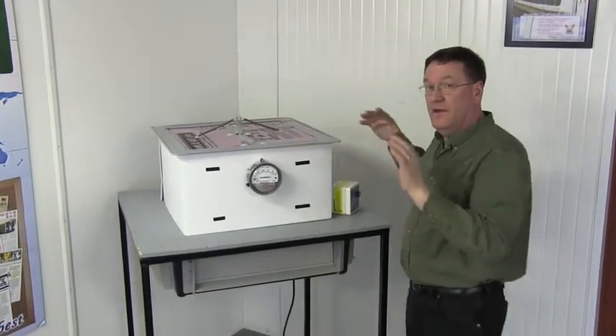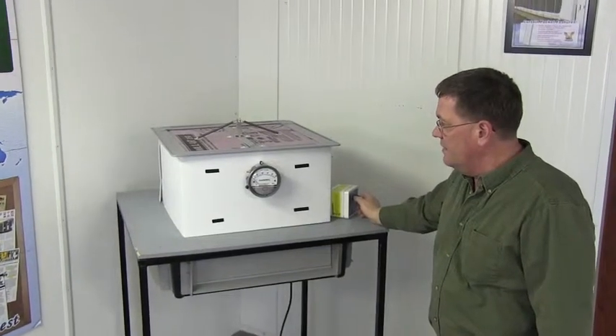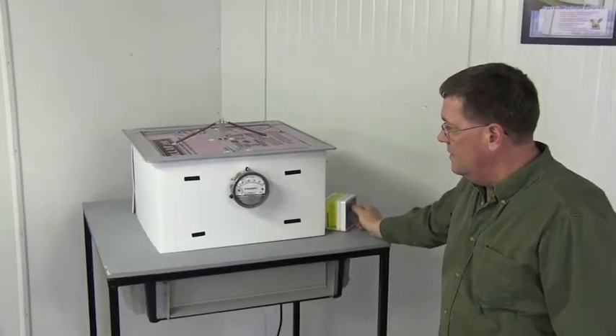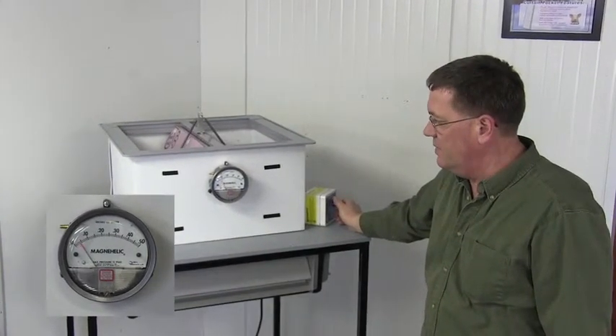You set this right on top of your attic sleeve that's already up in the attic. Once your fans kick on, it will suck these little doors open. They open at about 0.01 static pressure, so it's really easy to open.